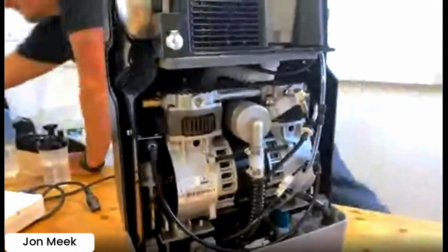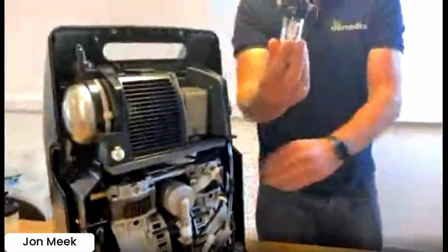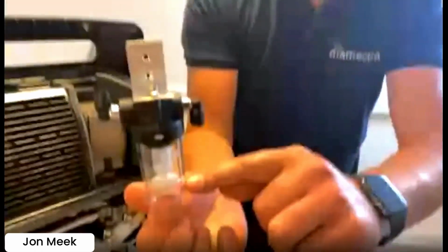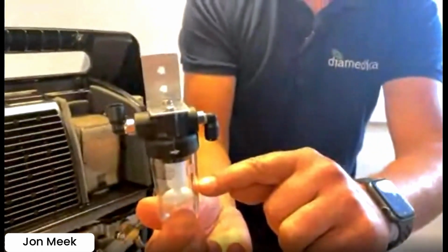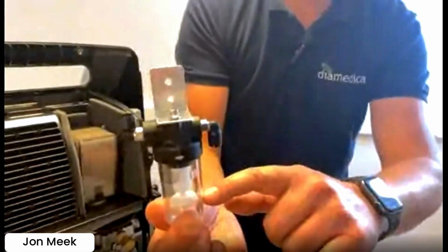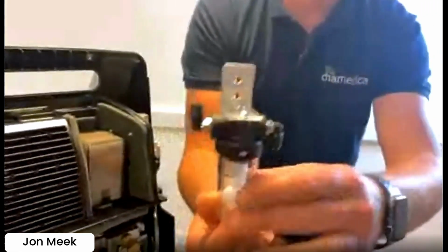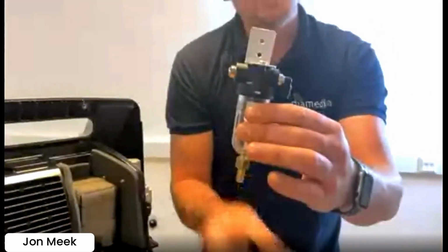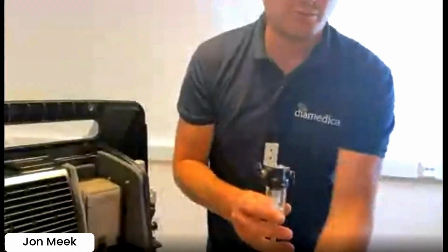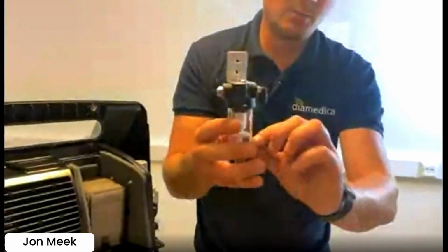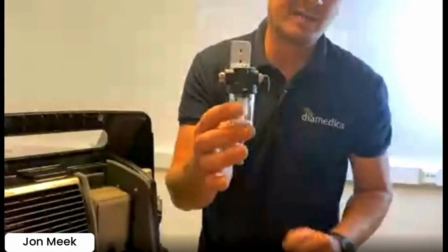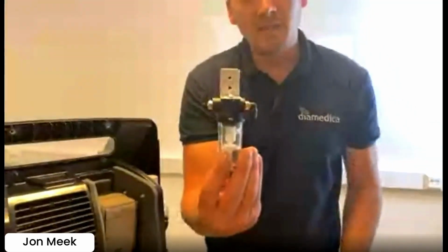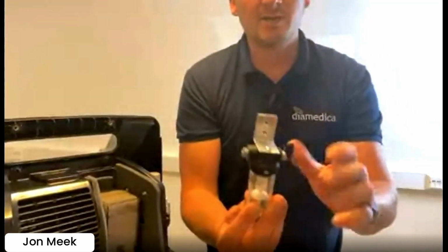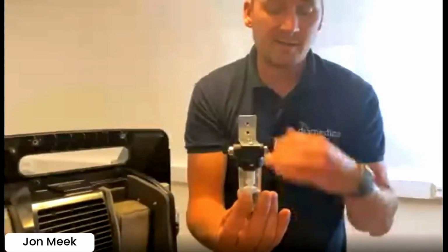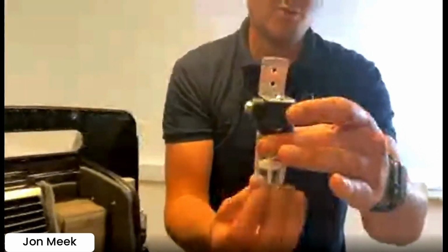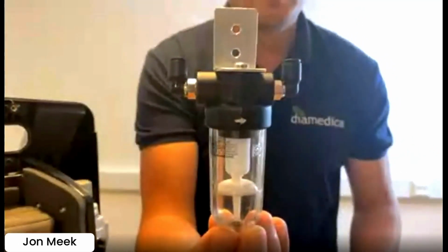So if I've just got one here. On here, you'll have a white disc. As it fills up, if it gets above the disc, it has failed. But once it gets to a certain level, it will lift the disc and allow the moisture under pressure to dissipate. So you won't see the moisture on the floor because it comes out as a mist. But once it gets up, it will automatically drain out of here. And you will see this condensate pretty quickly due to the temperature of these environments they work in, but they will remove a lot of moisture from the machines.